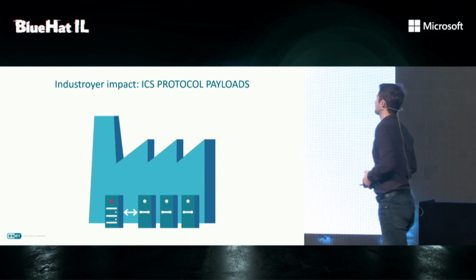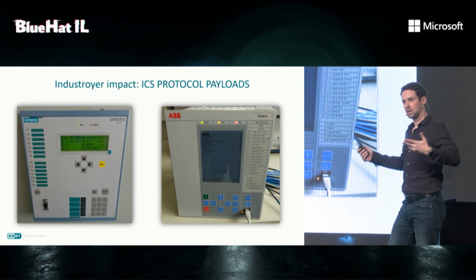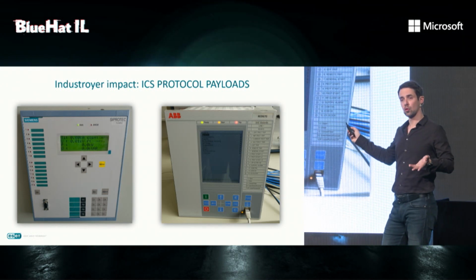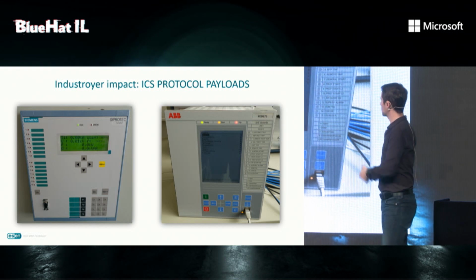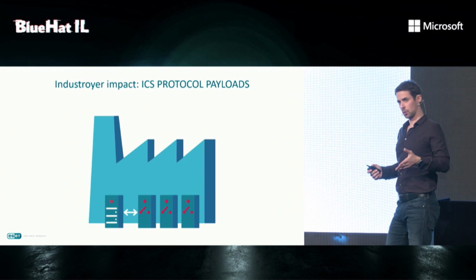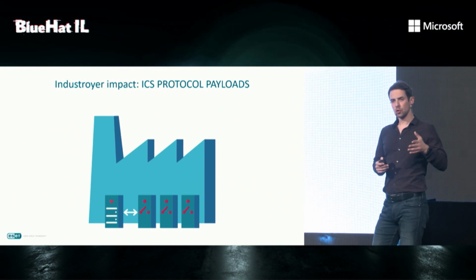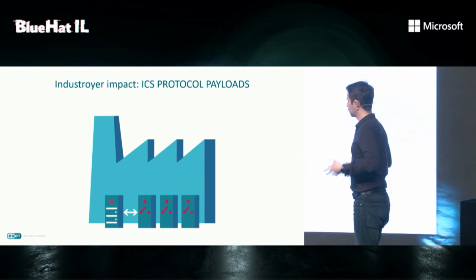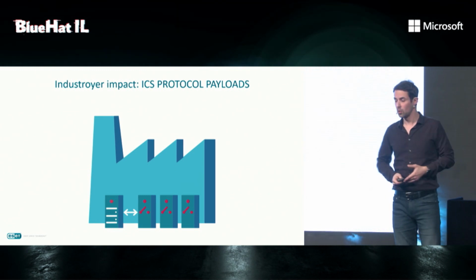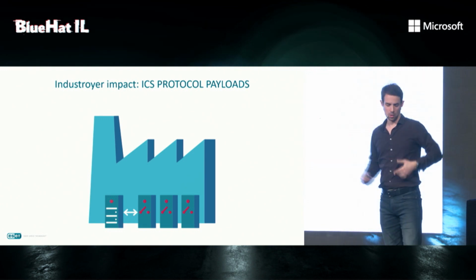So this is a substation, and we identified three main ways the Industroyer samples attacked these electricity distribution substations, or transmission in this case. So firstly, and most importantly, it could directly control the industrial hardware on site. So these types of boxes, protection relays, it could send commands to these devices. And it would do so using one of 4 industrial communication protocols. These were embedded in Industroyer as plugins. Now, Industroyer was abusing these protocols. There were no exploits involved, no software vulnerabilities in play, but you have to remember that all of these protocols were designed decades ago without security in mind, without the notion that all of this stuff would be connected remotely and exposed for remote and malicious access.